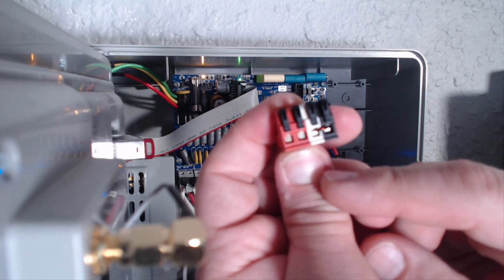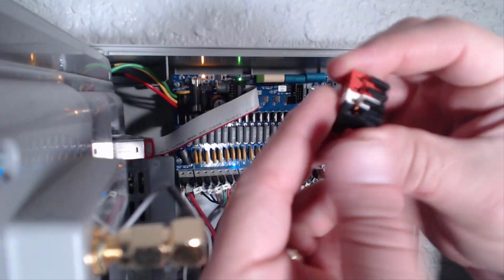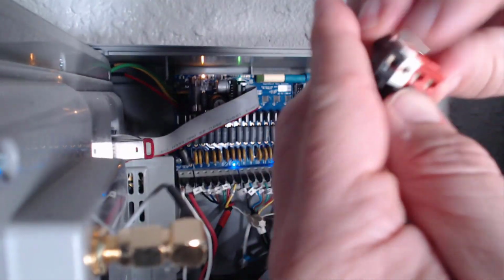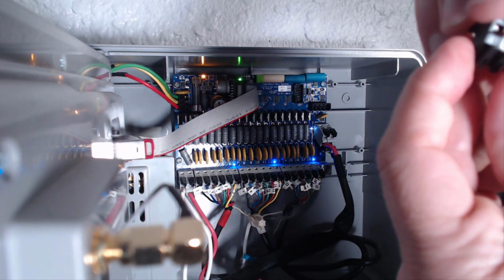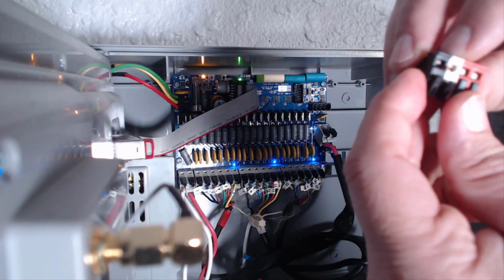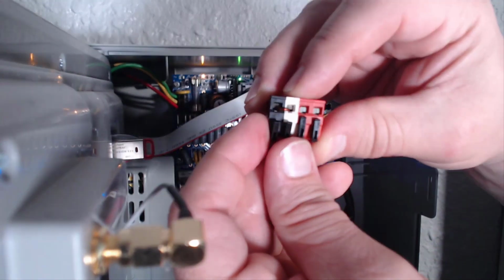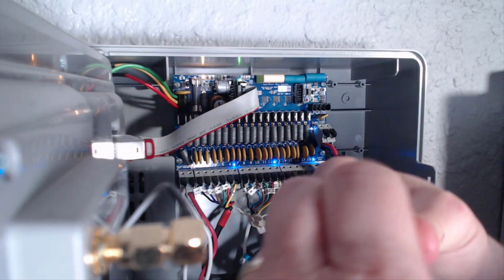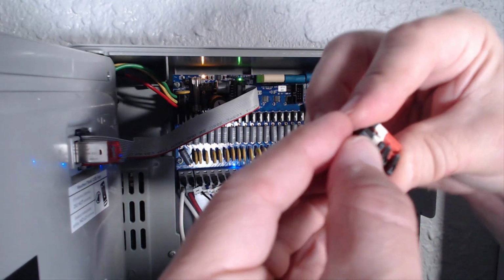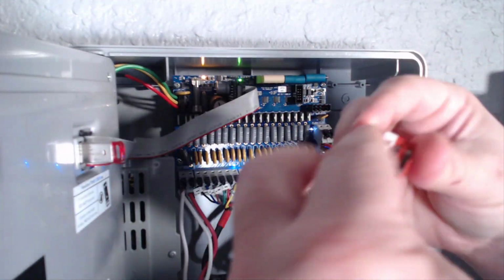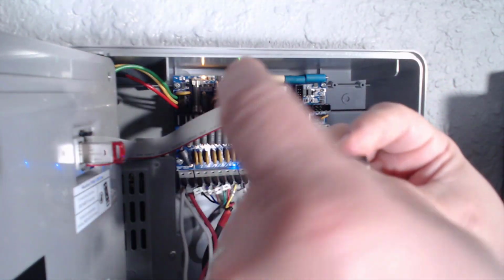They come factory with a jumper in it, which simulates a dry situation. Technically, when you get a rain sensor, when it gets wet it's going to create an open circuit, disconnecting it just like removing that jumper wire, and it's going to go into a rain event. Perfect, yeah, showing the jumper.